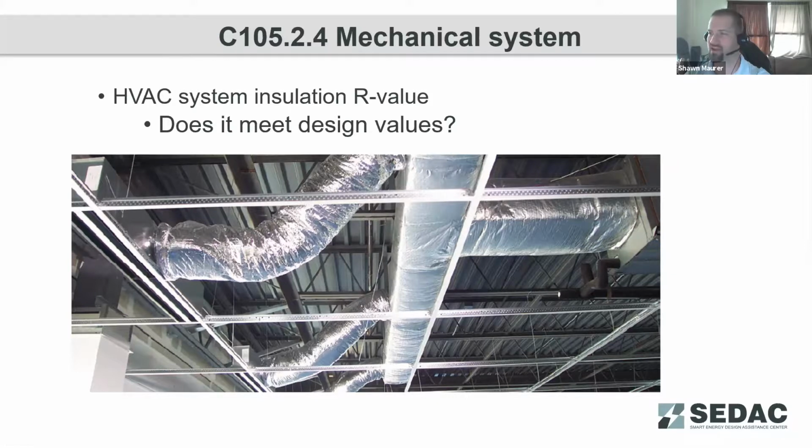They are depressurized. They are very, very likely to draw in outside air from envelope leaks. And as you draw in that outside air, you also draw in that uncontrolled humidity. We have seen instances where uninsulated ductwork has developed condensation and created what look like roof leaks on the drop tile ceiling. So again, usually if there is insulation on that ductwork above a T-bar ceiling or drop tile ceiling, it's there for sound dampening control.